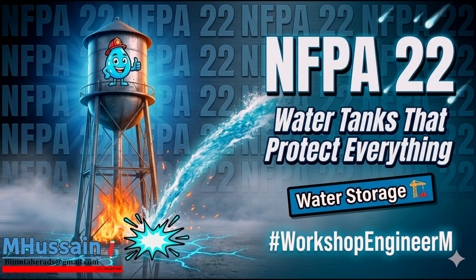Because the NFPA operates on a timeline of decades. Paint fades, chips, and degrades. Industrial adhesives fail in the constantly damp, fluctuating environment of a mechanical room. So it has to be permanent. A raised metal arrow, physically stamped into a riveted plate, is infallible. When a maintenance technician walks into that room 15 years after you designed it to verify the water-to-air ratio, they need an unalterable reference point.